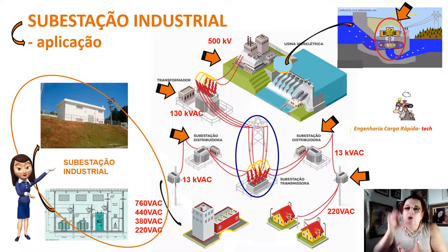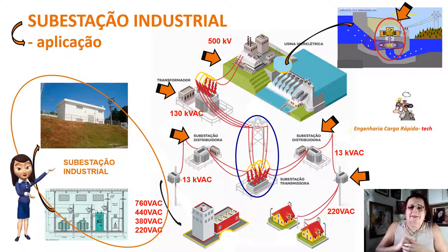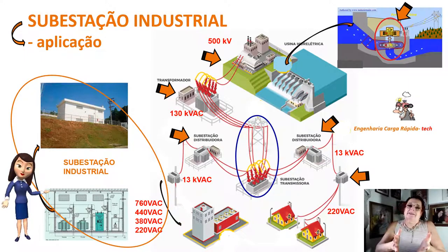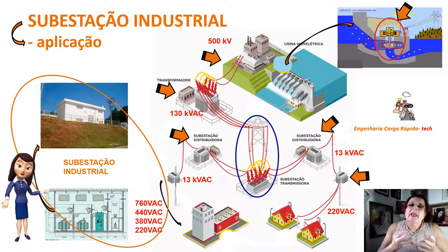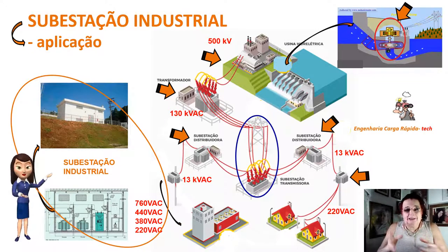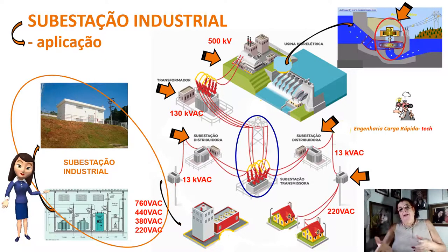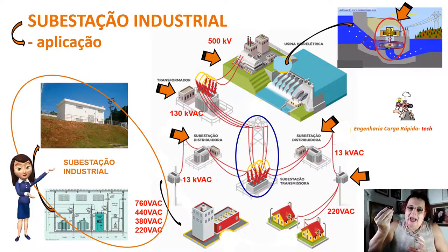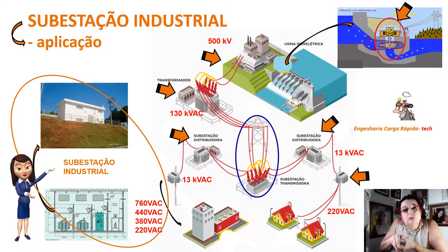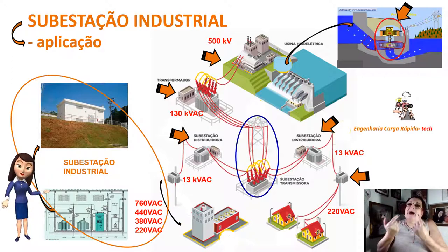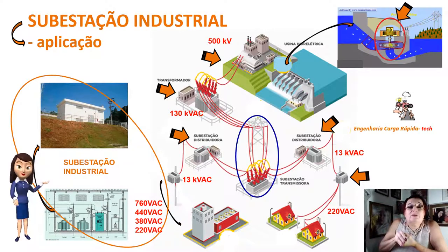A subestação industrial rebaixa os 13 mil volts para 760, 440, 380 ou 220 volts para escritórios. É comum que máquinas industriais operem com 440 ou 380 volts, pois quanto maior a tensão de alimentação, menor a bitola do cabo, tornando mais barato formar todo o circuito elétrico da indústria com cabos mais finos.